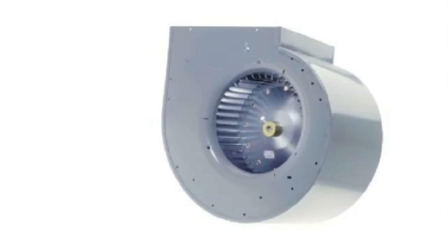A static pressure blower means it will move air against static pressure. Now what is static pressure? Static pressure is pressure that you can measure inside the ductwork. Even if you closed off all outlets to the ductwork, you would have a certain amount of static pressure that this blower could produce.